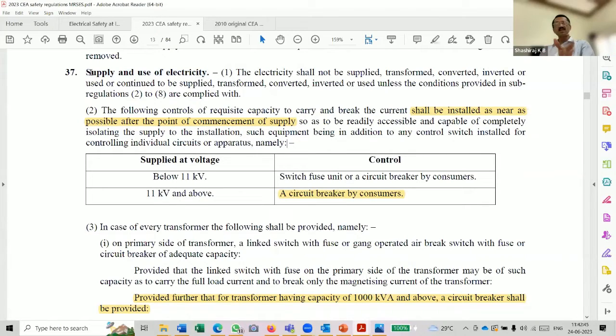No. See, that's precisely what I was trying to tell. 37 speaks generally of all the installations when it comes to supply by the supplier to a consumer. And 37.2 specifically speaks of the consumer protection because it is at the point of commencement of supply, and that definition, point of commencement of supply, applies only to the consumer. So 37.2 refers exclusively to the consumer, but 37.3 does apply to the DISCOMs as well.